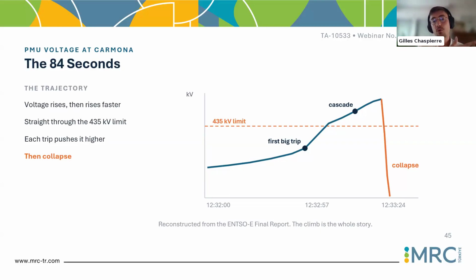And also, unfortunately, in the morning, some inter-area oscillations were visible. I will come back to that later. That leads to some, let's say, mitigation actions, bringing again the voltage higher. Unfortunately, at some point, the voltage was too high. And because of some improper protection settings, some units start tripping. But the problem is that when you start losing units that were themselves controlling the voltage and absorbing MVAR to make sure the voltage is not too high, you enter a positive feedback loop again, and you get this acceleration of voltage increase, because losing MVAR capability further rises the voltage, leading to other tripping, further rising the voltage. Then it's the cascading impact.